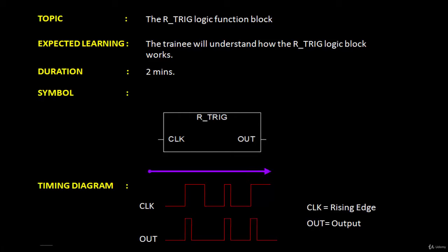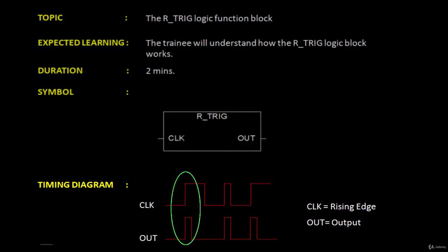The logic flow is from left to right, which will start with the input, the logic solve, and then the output. Looking at the truth table, output is a pulse if in01 is a logic transition from false to true.